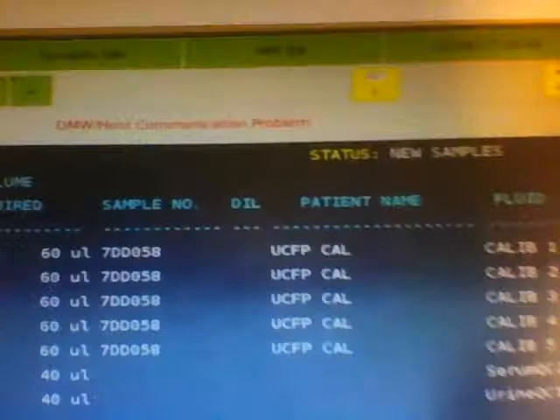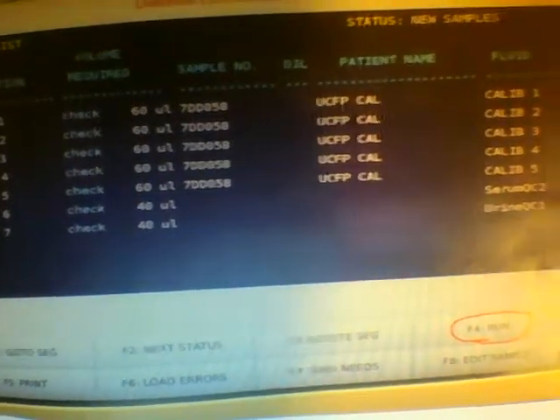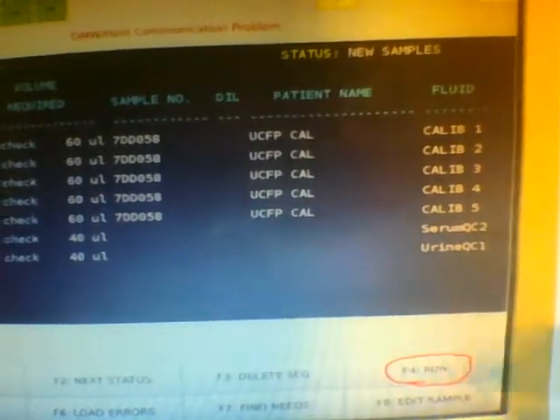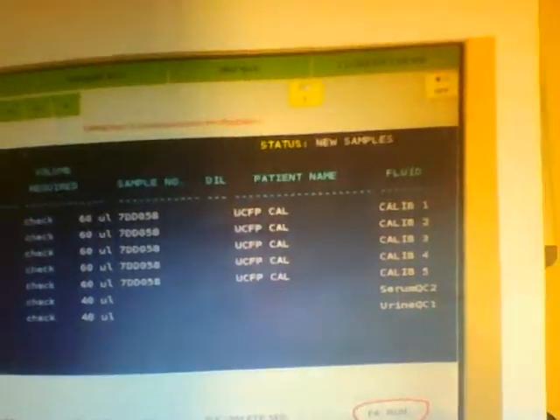you get to this menu right here. And again, this shows you your final screen, and this is a great final check to make sure you have the correct lot number for your calibration. It does not show you the reagent, but you'll know the reagent is not on there because it will not run a lot number that doesn't have the reagent on board. And the last thing you do is push F4.